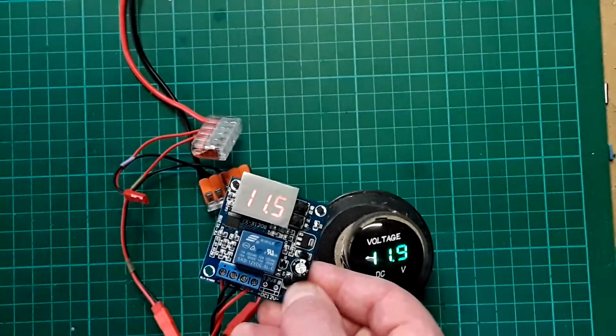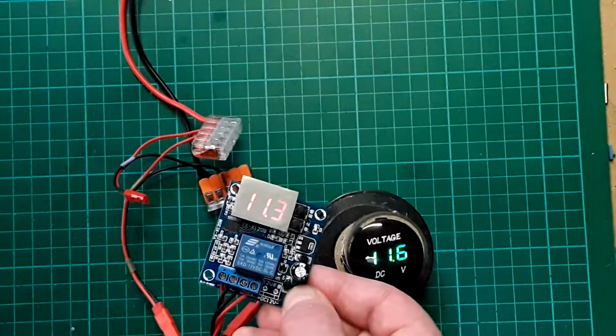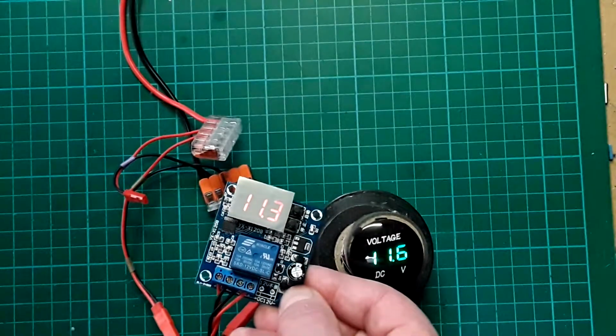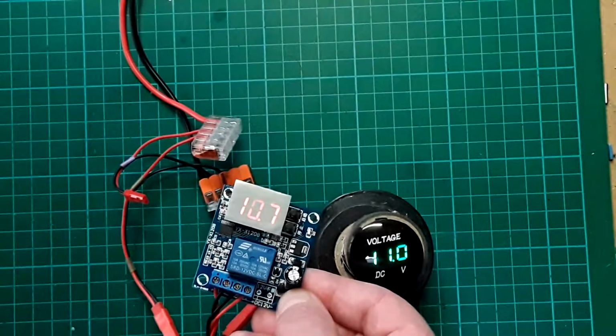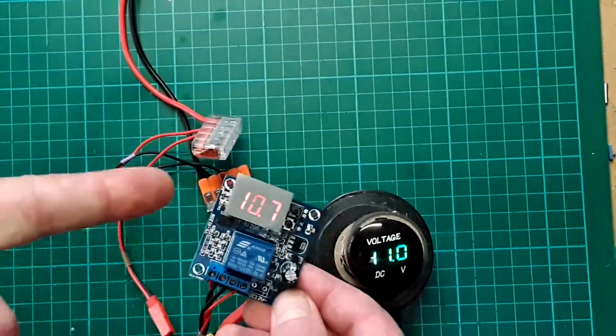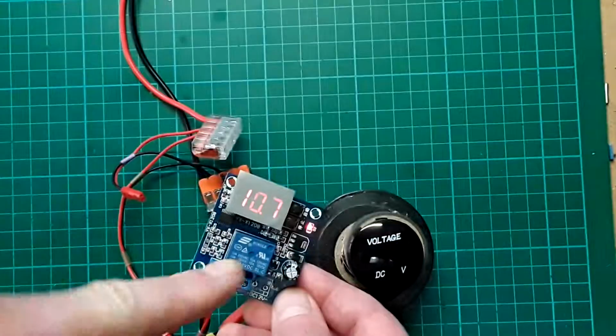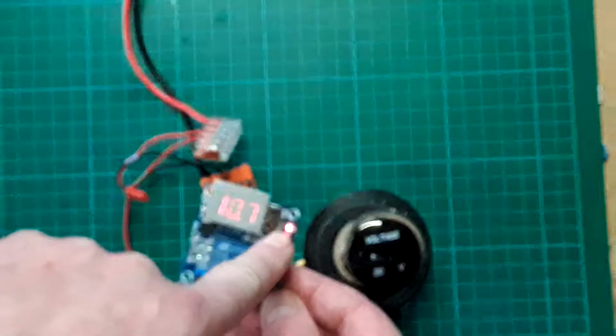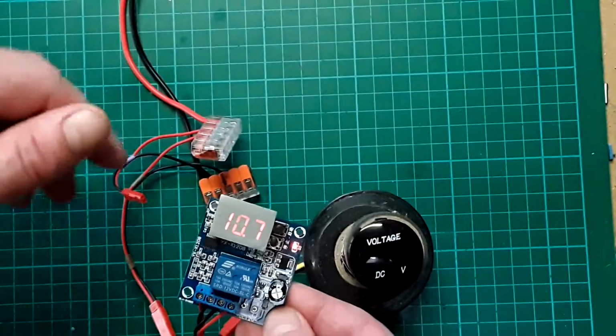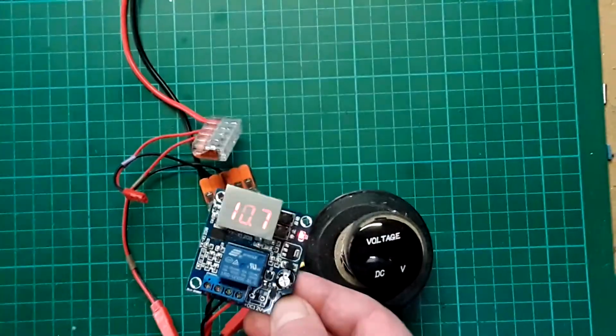Down we go, and just above 11. Now we're just below 11. It's not done anything yet, but after a set time period, the fault light comes on and the load is disconnected. So as well as the hysteresis, you've also got a slight time delay as you're going downwards.